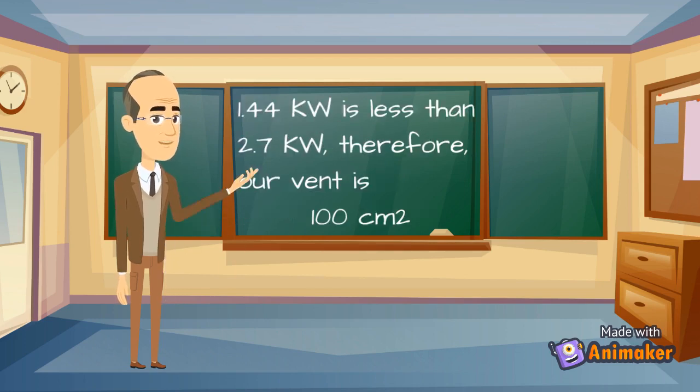Our appliance is 1.44 kilowatts net. This is less than 2.7 kilowatts net, which is the maximum allowed before adding further ventilation. So we only need 100 centimeters squared of permanent ventilation.